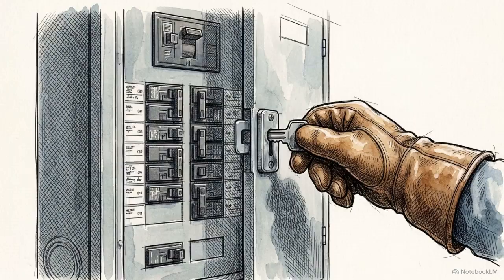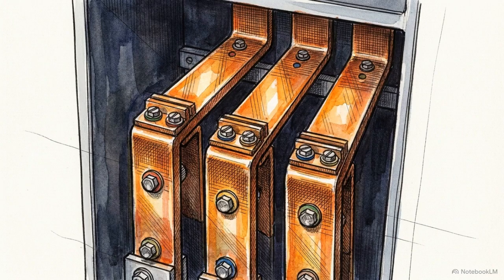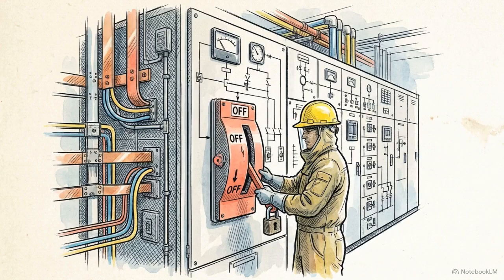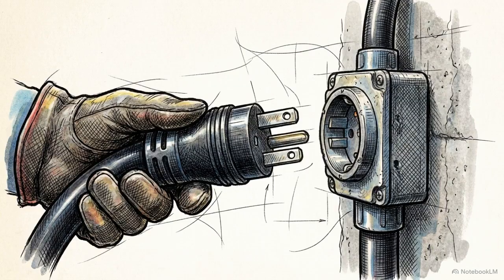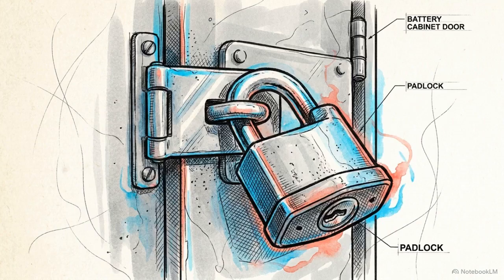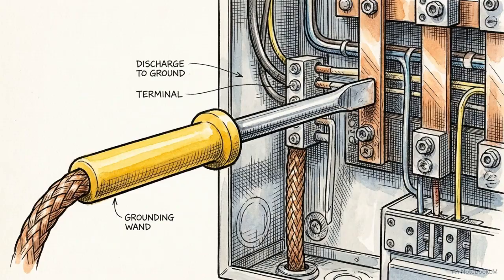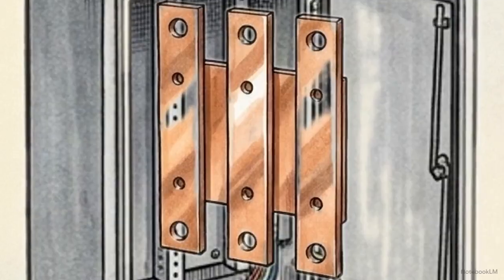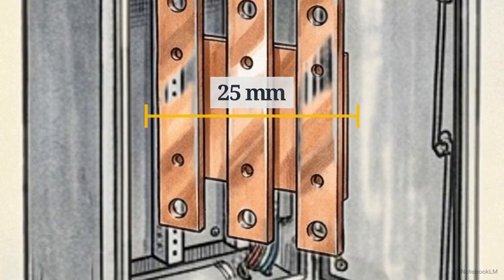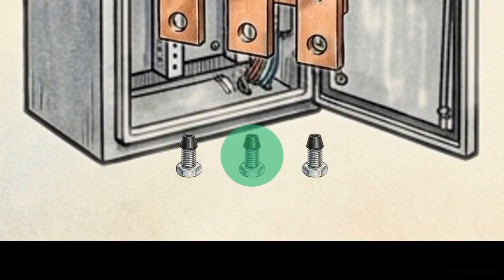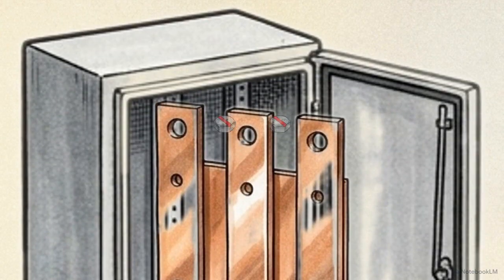The testing sequence begins by proving the physical isolation and insulation integrity of the DCDB's internal bus bars, the solid copper pathways that carry the main current. The panel is mechanically isolated from all external power sources. This includes disconnecting battery chargers, isolating the main battery banks, and removing any capacitive backfeeds that hold residual charge. Next, engineers perform a visual inspection. They verify proper busbar clearances, check the integrity of cable glanding, and confirm that torque marks are present on every tightened terminal.